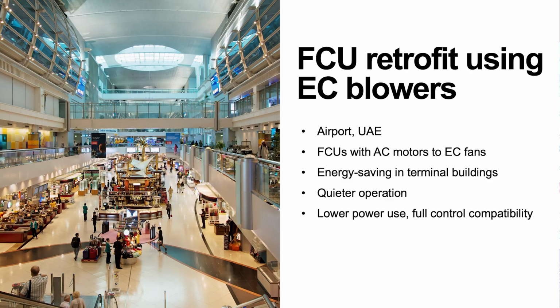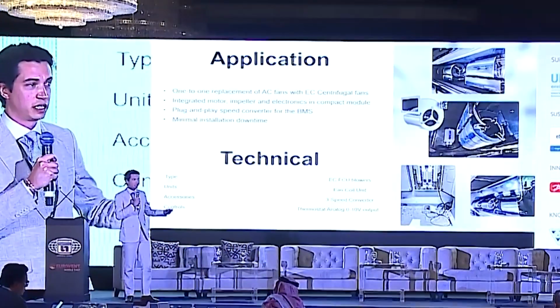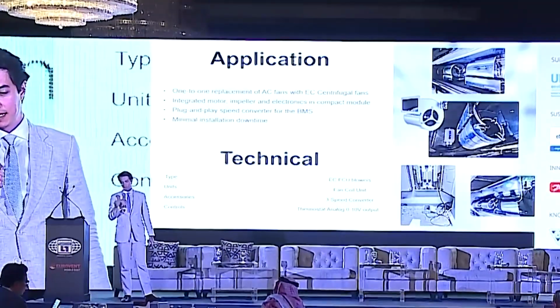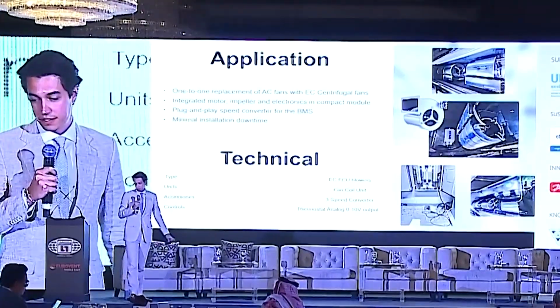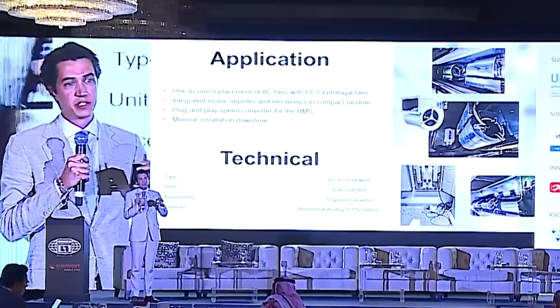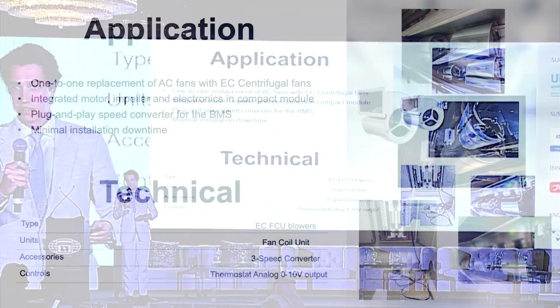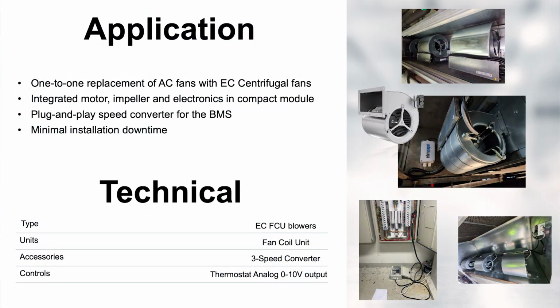For this application we brought our FCU EC blowers, forward curved, with an integrated EC motor in the fan. We replaced the unit with EC fans, but with a 3-speed converter to keep control directly on the existing thermostat. This gave minimum downtime installation and much better noise level.